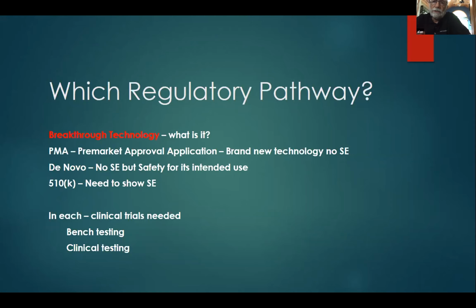The 510K is the easiest route for devices, and wherever we can, we try to go the 510K route. It's the cheapest, it's normally the quickest, and you normally have to show some kind of substantially equivalent. Now, if you're saying you have AI, and there was no other AI, right now the FDA is looking at any device with AI has to go through de novo. The first device of that kind, using AI technology, normally has to go through the de novo route at this time. The FDA is putting all AI into de novo.